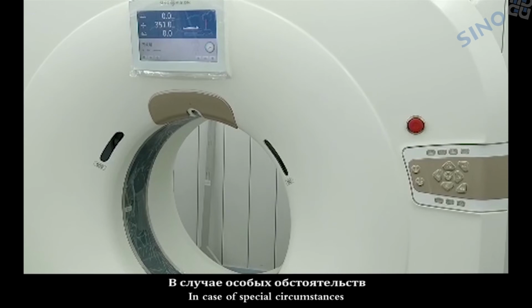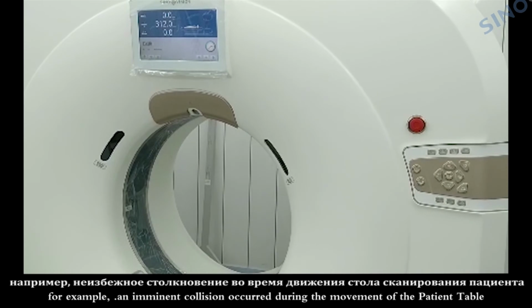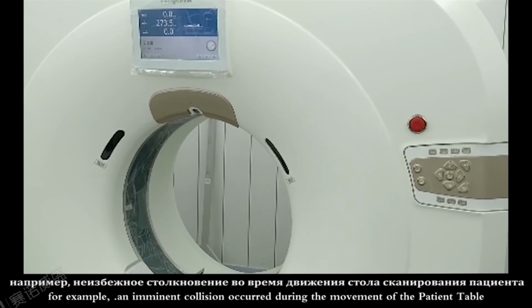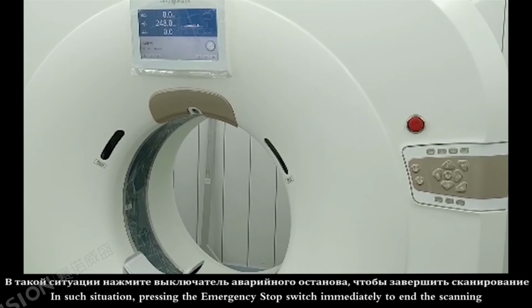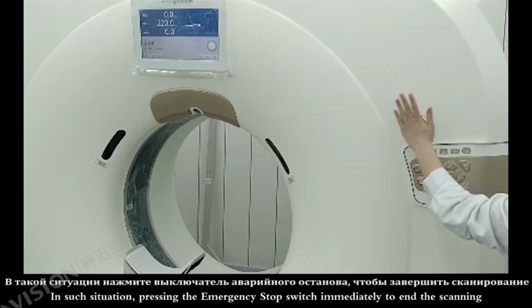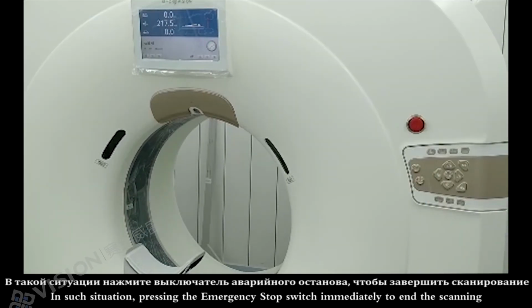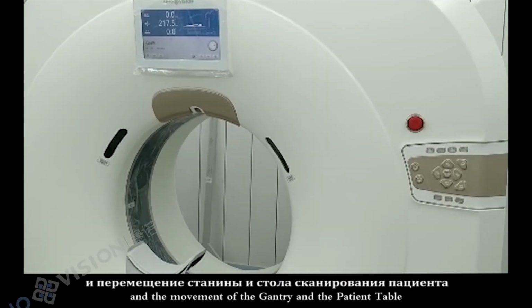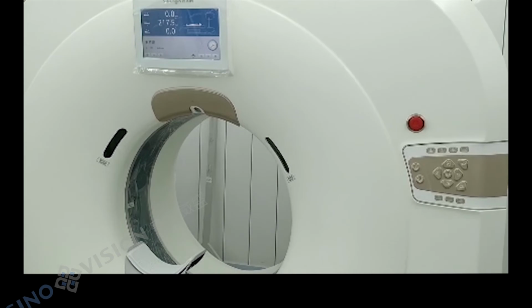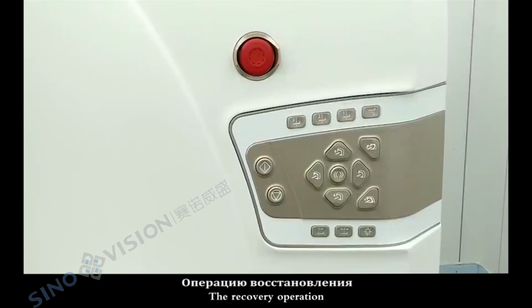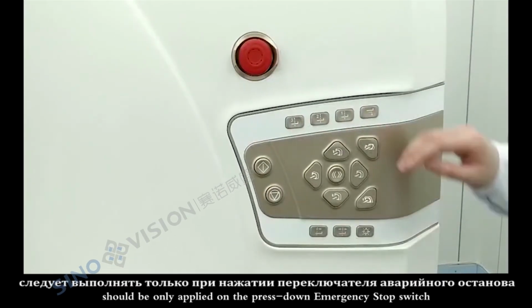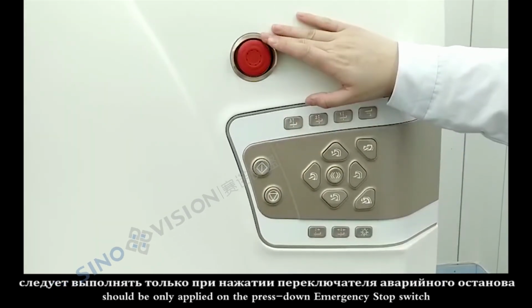In case of special circumstances, for example, an imminent collision occurred during the movement of the patient table. In such situation, press the emergency stop switch immediately to end the scanning and the movement of the gantry and the patient table. The recovery operation should be only applied on the pressed down emergency stop switch.